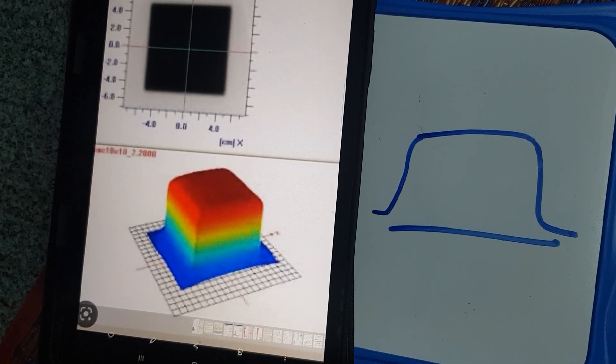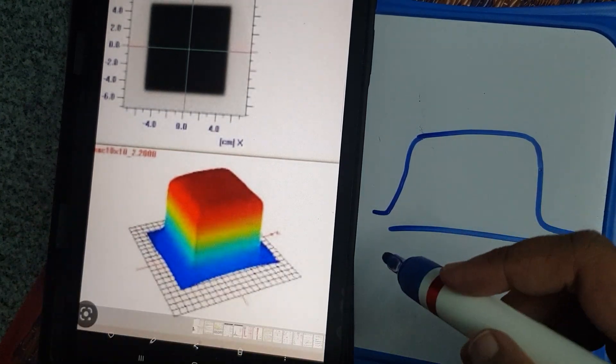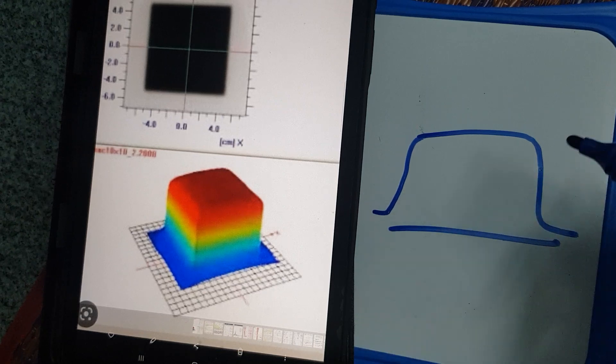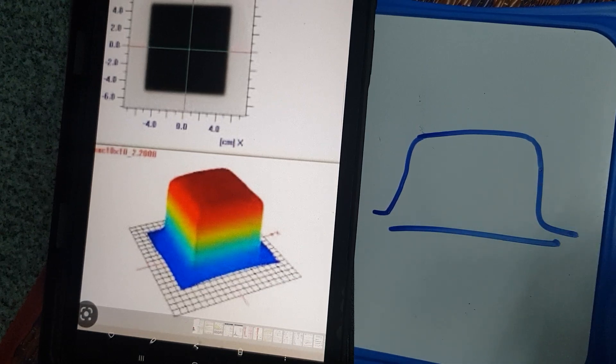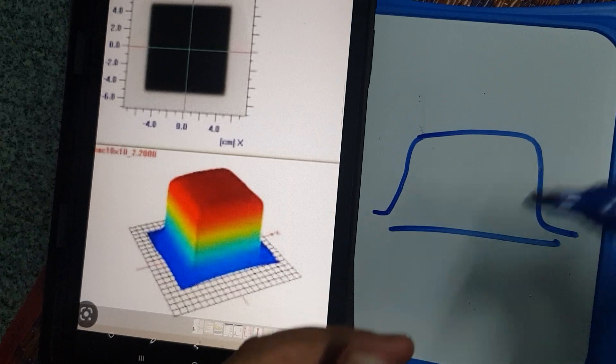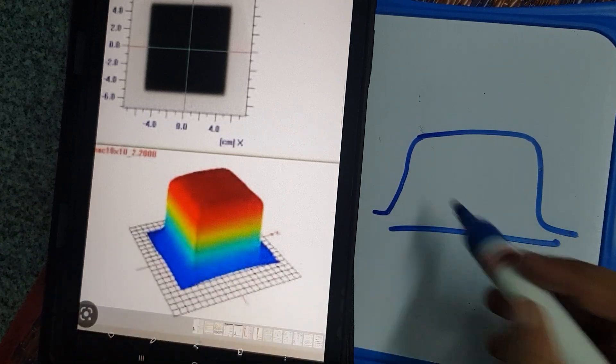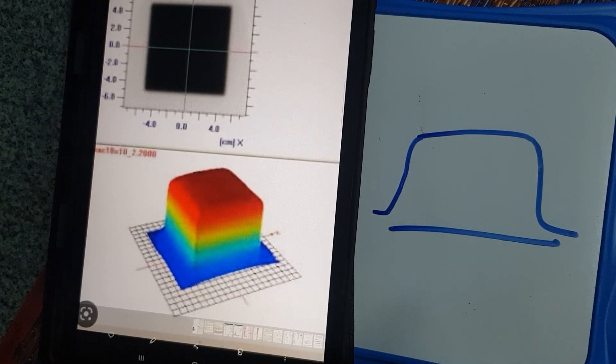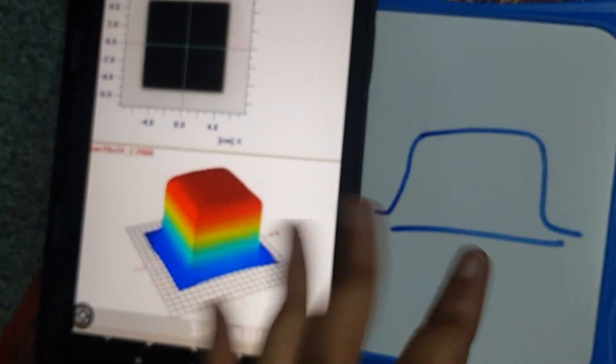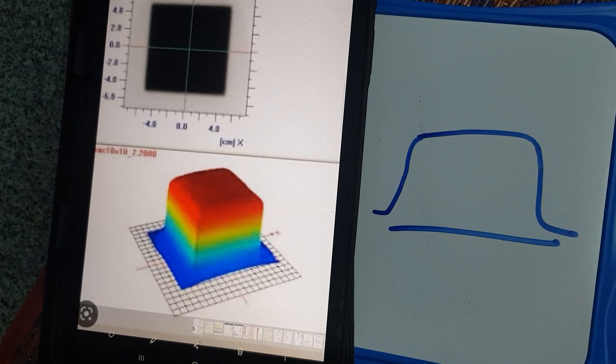In a beam profile, we know that we measure for flatness and symmetry. Flatness, we know that is the expression of difference between the maximum and the minimum dose across the beam profile at a particular depth.